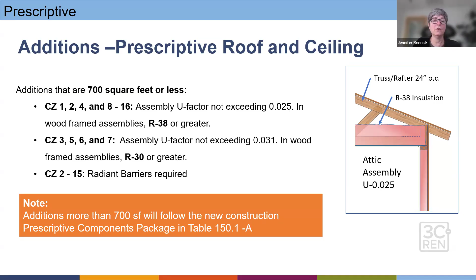The one thing a lot of folks are surprised by - this was true last code cycle and it's true this cycle - is that altered ceilings should be insulated to an R49, or a weighted U-factor of 0.02, which gets triggered in climate zone 4 and climate zone 9, part of our Tri-County region. Specifically, it's been shown cost-effective to add more attic ceiling insulation than R30 or R38 when you're redoing the whole attic and ceiling.